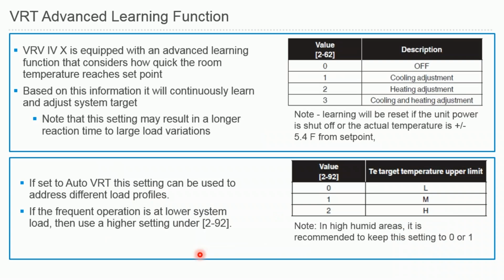And for VRT, we're adding a new function with VRV4X. Now it will include this advanced learning function that you will be seeing different field settings for in this slide. So basically, the logic will be looking at the last few cycles or so, and see how quickly the system is going into thermo on or off mode. Based on this, after analyzing the operation, the VRT will adjust itself, and it will try to get to high TE evaporating temperature levels. And when it does that, it will still satisfy the load without any reduction in capacity.